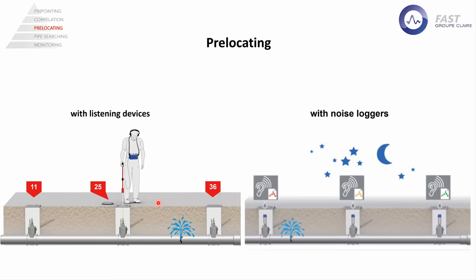And of course, a much better working principle nowadays is the noise loggers, which do all this job during a 2-hour period, not only a fraction of this. Usually the people walking around in the network don't have much time, so they open up a chamber, listen maybe for 1 or 2 minutes maximum for the sound, and then go to the next spot.